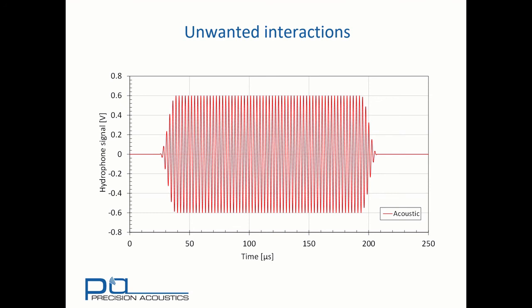It's also important to realize that with longer signals, we have the possibility for unwanted interactions. Consider here an idealized tone burst as shown. This is a low frequency wave of many cycles, and in fact is of duration close to 150 microseconds. But because the measurement location is relatively close to the transducer, propagation delay between the transducer and the receiver is only 25 microseconds.